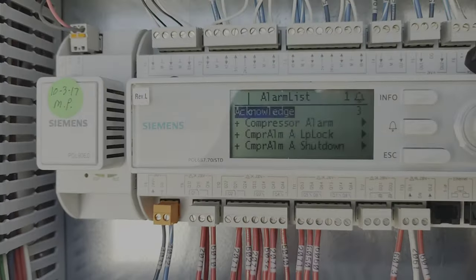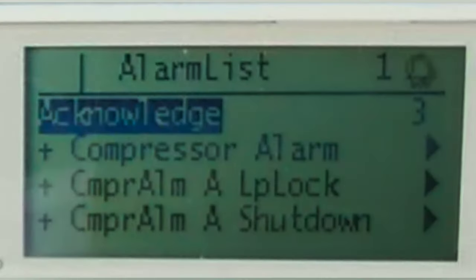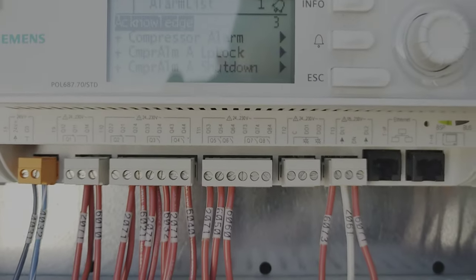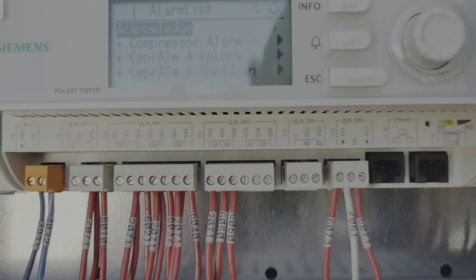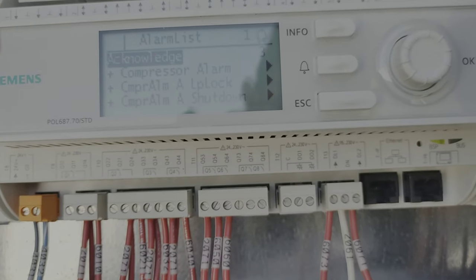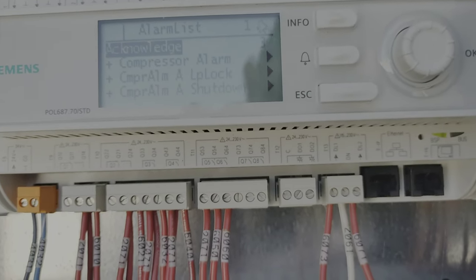Inside we got this control board and it has three alarms right now. Compressor alarm, compressor alarm, compressor alarm. So LP lock - I'm going to assume that's low pressure.